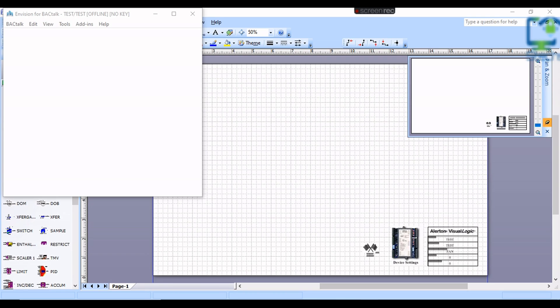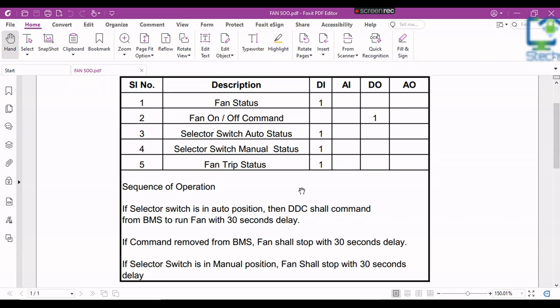You can see the sequence of operations here. If the selector switch is in the auto position, then DDC shall command from BMS to run the fan with 30 seconds delay. If the command is removed from BMS, the fan shall stop with 30 seconds delay. If the selector switch is in the manual position, the fan shall also stop with 30 seconds delay. These are the sequence of operation and the point list for the fan control.